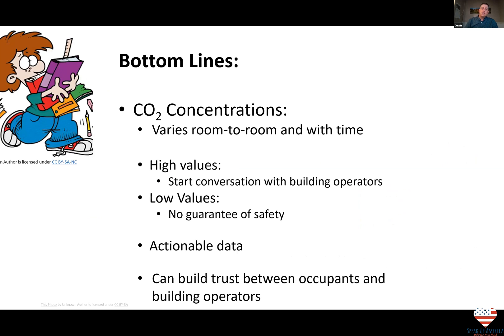The bottom line is that CO2 concentrations vary with time, room, season, and weather pattern. A single measurement from a few minutes is unlikely to capture the dynamic range or give actionable data. High CO2 measurements do not necessarily mean there is a risk, and low CO2 values do not signify that the space is safe — only that it's safer. CO2 monitoring of ventilation is but one component of an overall risk reduction strategy that includes portable air cleaners and HVAC filtration. I'll turn it back to David.